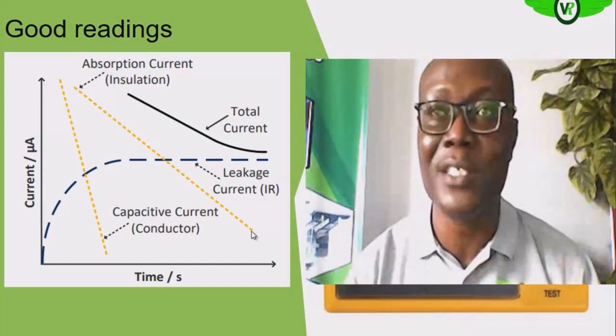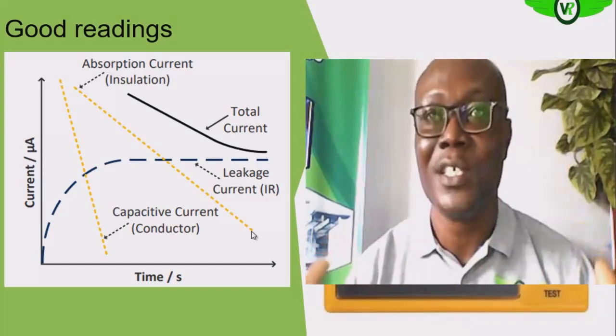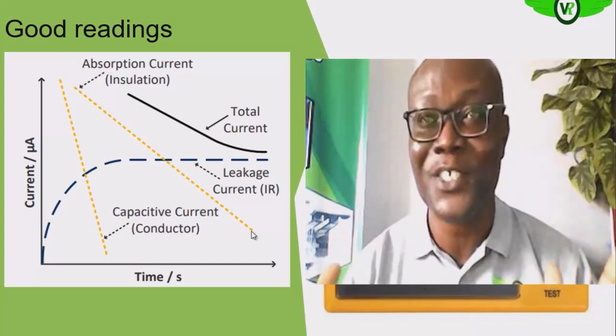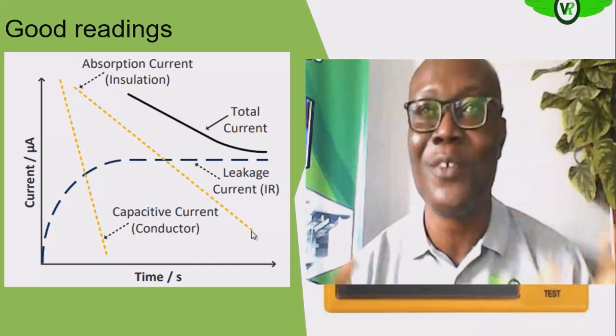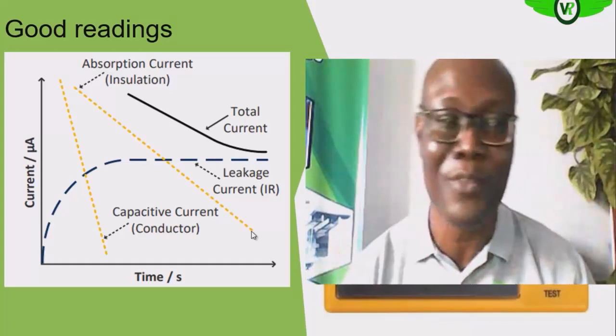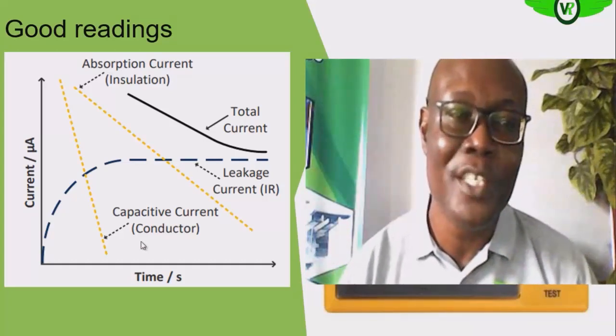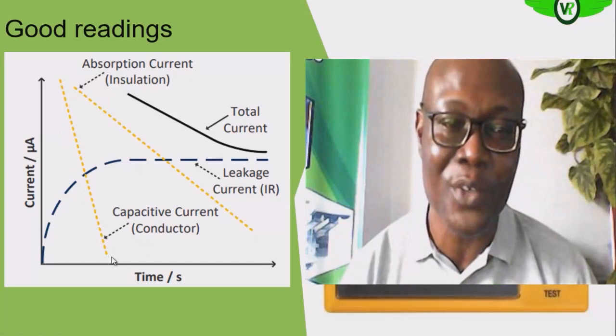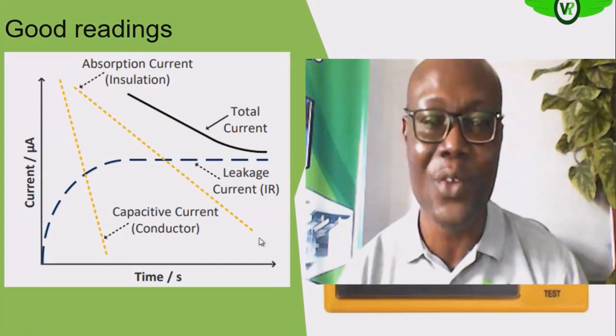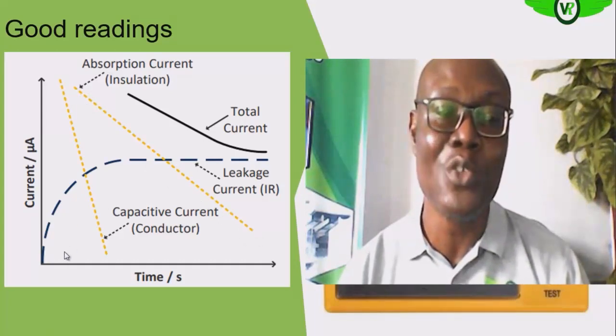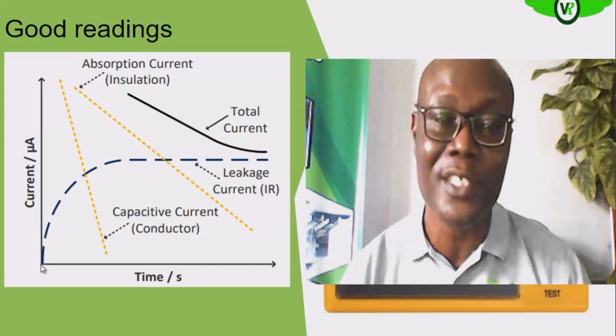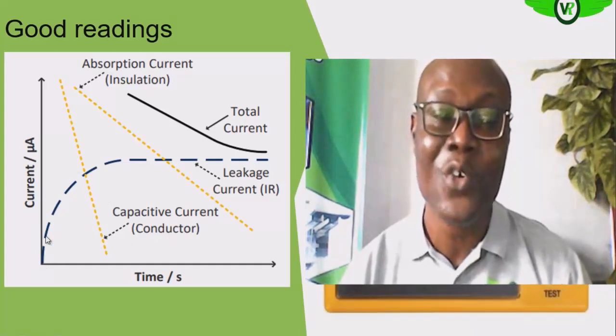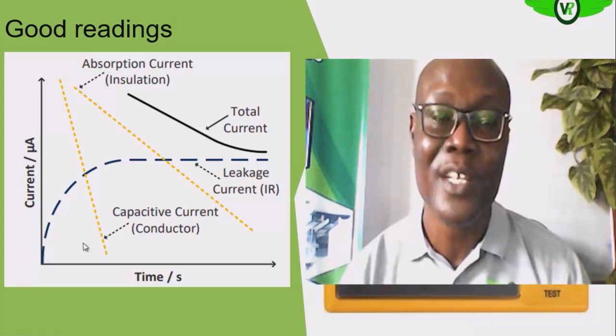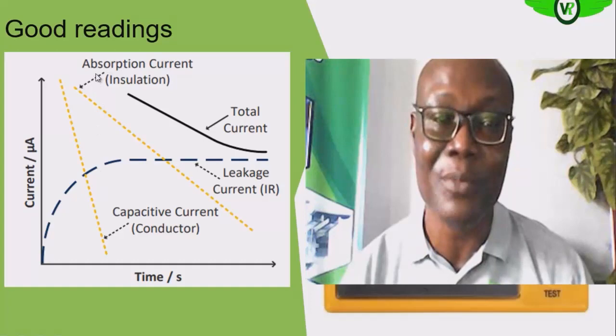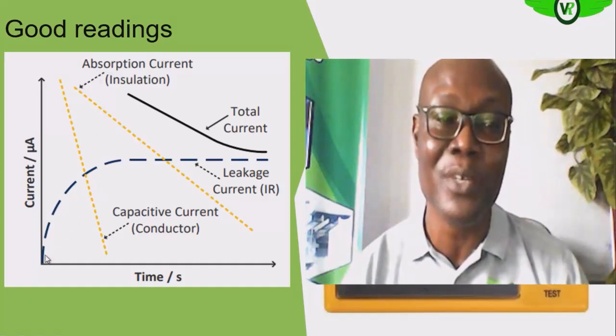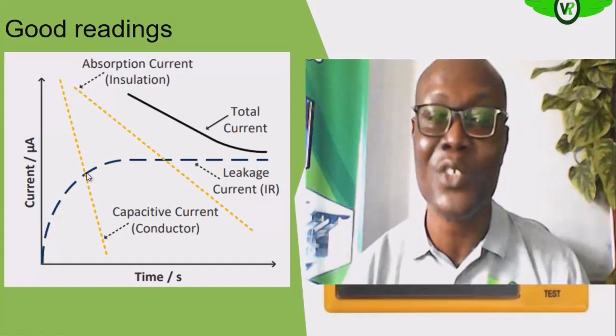Okay, but the capacitive current, that one takes, because once the plates that is created, so to say, we will see it later. Once it is fully charged, there will not be flow of current again. So this will dissipate or disappear within a few seconds, and then this will disappear after some seconds. Okay, so you see that once you inject your DC voltage and you rush to take readings, the reading that you will be taking will be inclusive of the effect of the capacitive current, the absorption current, and also the leakage current. And even at this point, you see that the leakage current has not risen to the full value.